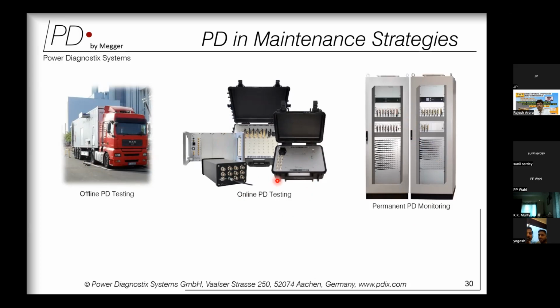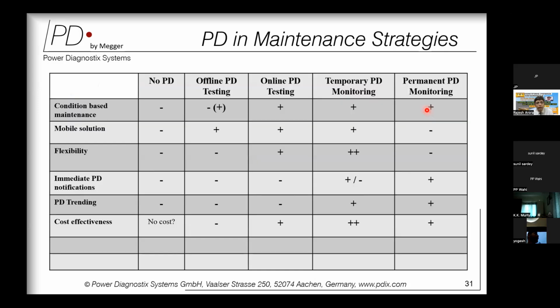Also, it's cost effective. When we talk about a permanent installation, meaning a 24/7 monitoring system, it is the best form of PD measurement, but it offers less flexibility. If you have multiple assets, you will need multiple systems, and they are quite costly. So both portable and permanent offer their own plus and minuses. So Power Diagnostix, or Megger as a company, we have developed a new platform called temporary partial discharge monitoring, which offers you the best of both worlds. You have a portable instrument, yet it offers you all the measurement possibilities of a permanent monitoring system.